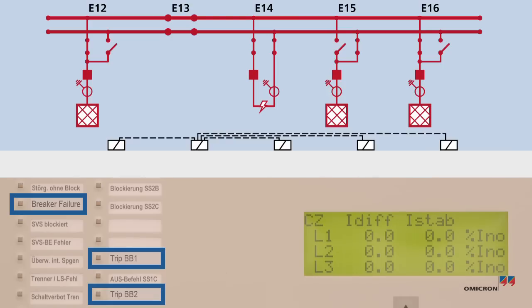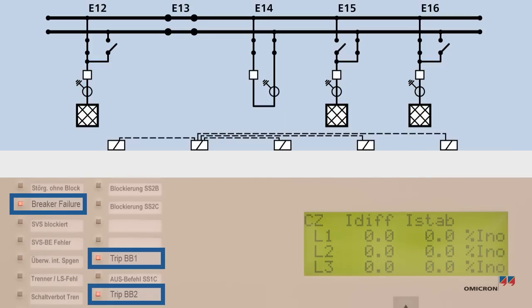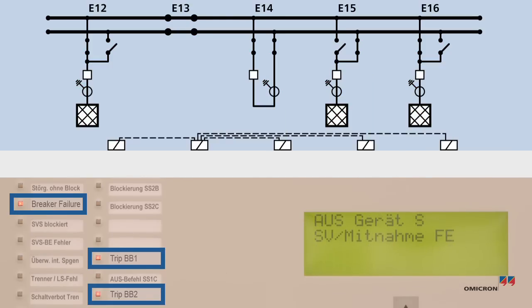As expected, the protection finally trips the complete bus bar, since it is unable to clear a fault within the dead zone selectively.